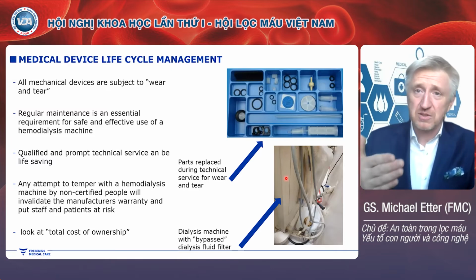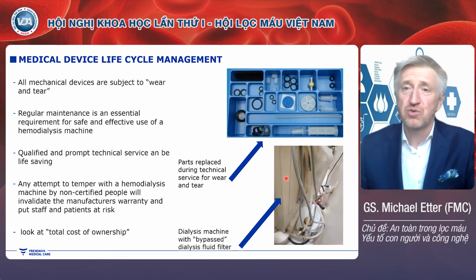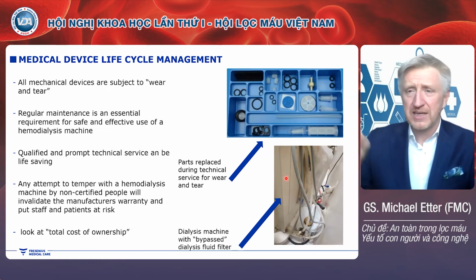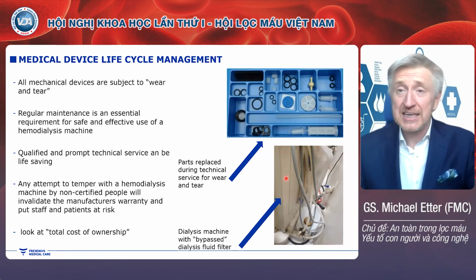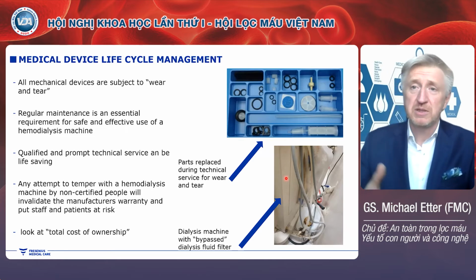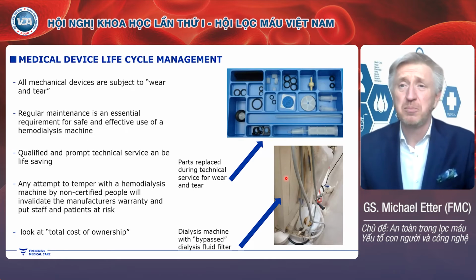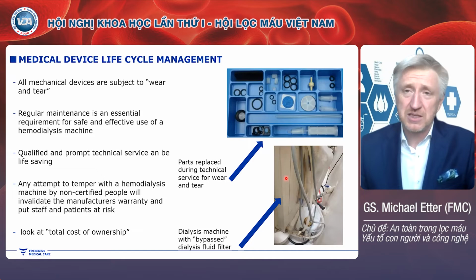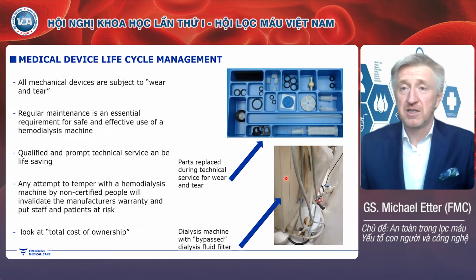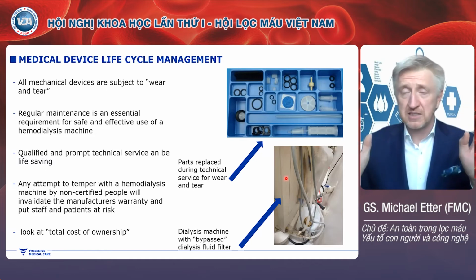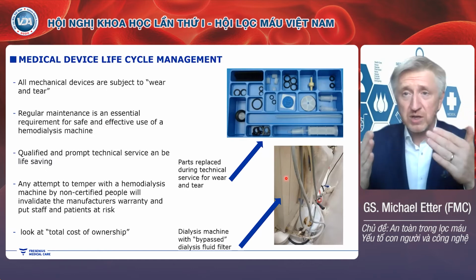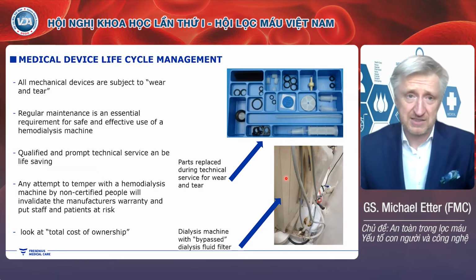This is part of the process. For example, you see this blue tray, these so-called O-rings. They can wear off over time, so they need to be replaced on a regular basis. That's an important part, and you need to consider that you don't stop maintaining your device. Make sure that the people who take care of your device are qualified and certified by the manufacturer, because, as I said, there are many types of dialysis machines and many are very good, but you need to have the individual knowledge for every device.